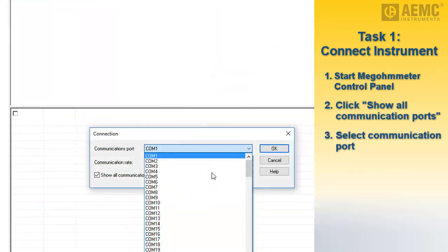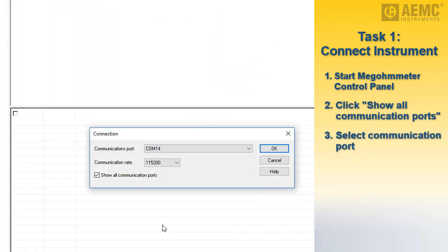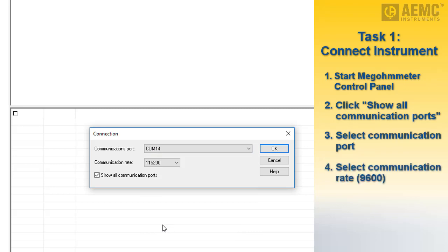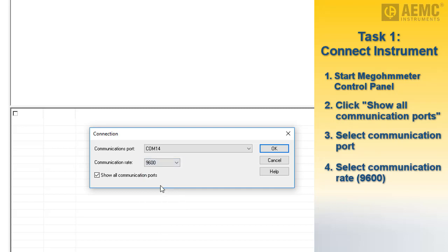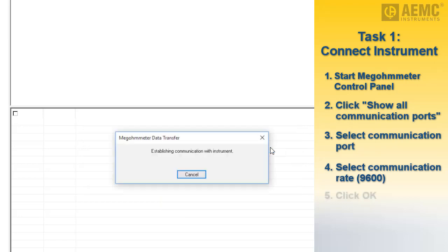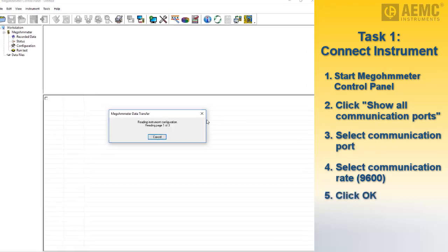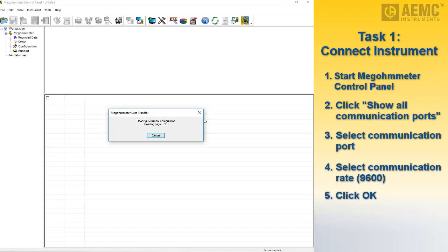Select this port number from the Communications Port drop-down list. Next, select the communication rate. For the Model 1060, the default baud rate is 9600. This can be changed on the instrument. If you do so, ensure the baud rate you select in the control panel matches the instrument setting. When you have completed both fields on the communication dialog, click OK.